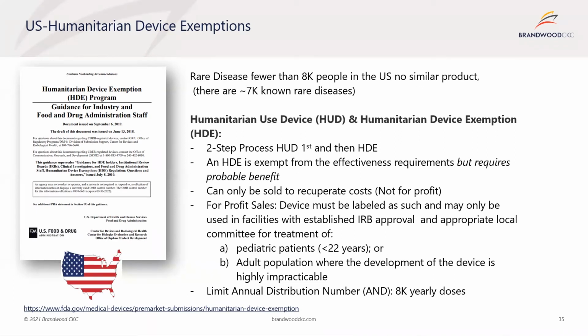An HDE is exempt from the effectiveness requirements, but requires probable benefit. What that means is that by default, these products are PMA, class 3 products. And the FDA would really apply risk assessment to the risk-benefit ratio on approval of the products. There's not a full requirement that the product needs to be clinically validated, but that there needs to be a probable benefit. And I'll jump a little bit more into what that means with some more details.